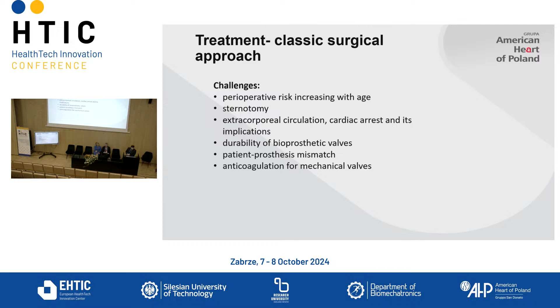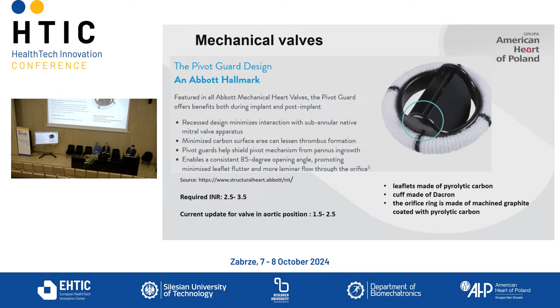So starting from the last, almost all mechanical valves have two discs, leaflets made of pyrolytic carbon, a cuff made of Dacron, and the orifice ring is made of machined graphite coated with pyrolytic carbon. And as I said before, those valves require anticoagulation. The INR, international normalized ratio, means basically how much longer our blood needs to clot to be safe for this valve. For most of the valves, the required INR is 2.5 to 3.5, so that means that the patient is much more prone to bleeding. There is a current update for the aortic valve position that 1.5 to 2.5 may be sufficient, so that's a little bit safer, but it still makes the patient, especially an older patient, prone to bleeding complications.